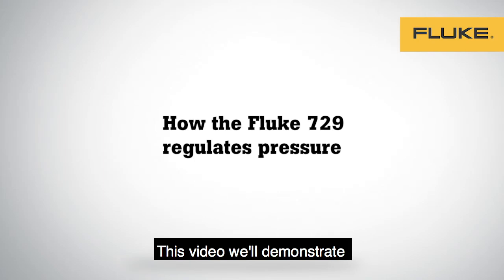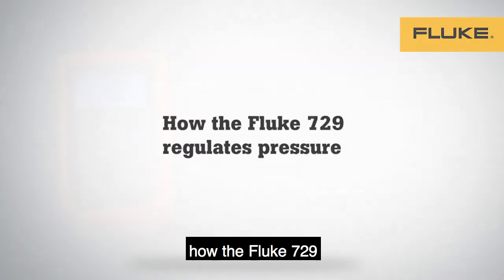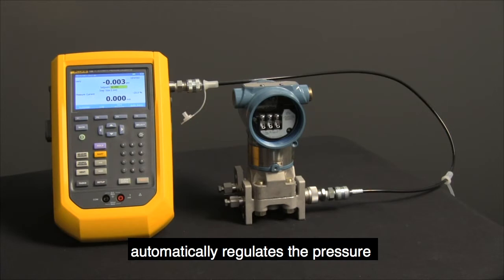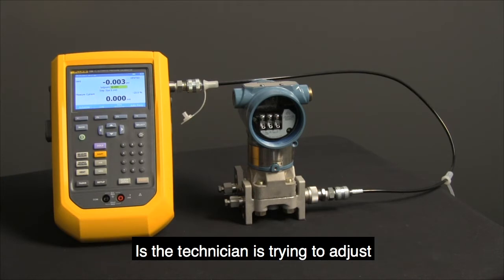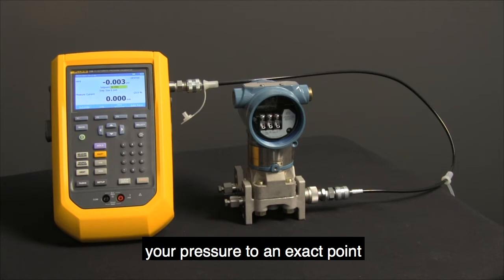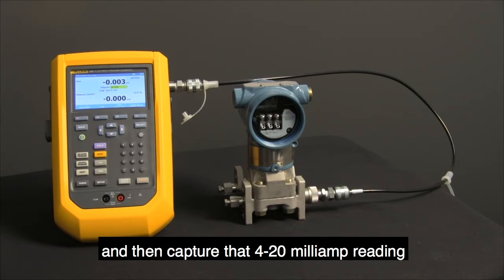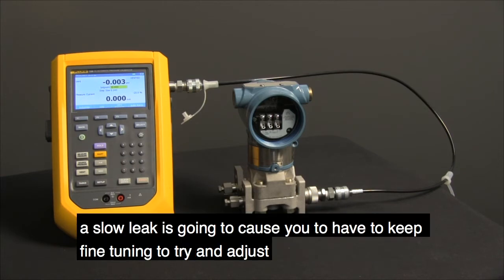This video will demonstrate how the Fluke 729 automatically regulates pressure even during a slow pressure leak. One of the main difficulties you'll see in the field as a technician is trying to adjust your pressure to an exact point and then capture that 4-20 milliamp reading. A slow leak will cause you to keep fine-tuning to adjust.